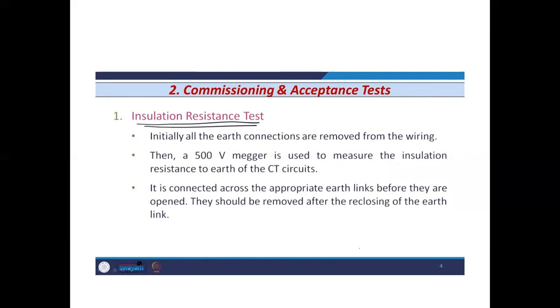A megger is the instrument that is used to measure the insulation level, especially for cable insulators. In a megger, we have a generator-type arrangement. We rotate the handle or the rotor, which provides mechanical energy to the generator, and as a result electrical energy is produced, which flows through the insulator to be tested. In this way a resistance is given by the megger. So this is the brief working principle of the megger.